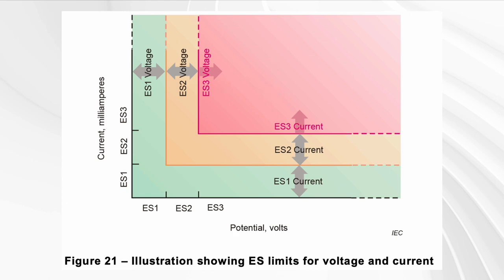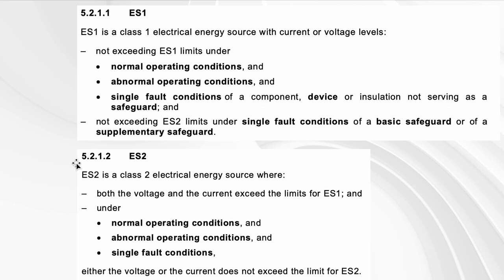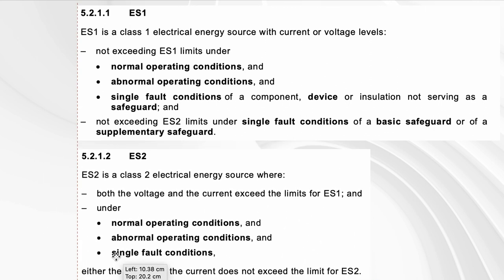ES2 itself exceeds ES1 in at least one dimension, but in all conditions either the voltage or the current does not exceed the ES2 limits. If one of them — voltage or current — exceeds the limit for ES2, even just in a single fault condition, then it is ES3. Basically, ES3 is everything worse than that.